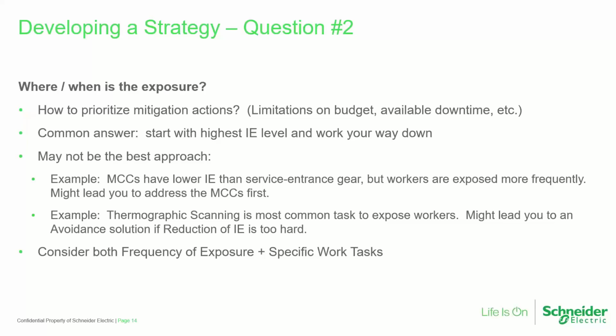The exposure was much more frequent in those locations. So even though the energy levels were lower, at least in their mind, if they could reduce the energy levels there, even though they weren't quite as bad as they were at some other locations, that gave them really more bang for your buck, if you will. They would have more immediate benefit out of that by protecting the locations where exposure was most frequent. Then once we got those done, we moved on to those other locations.